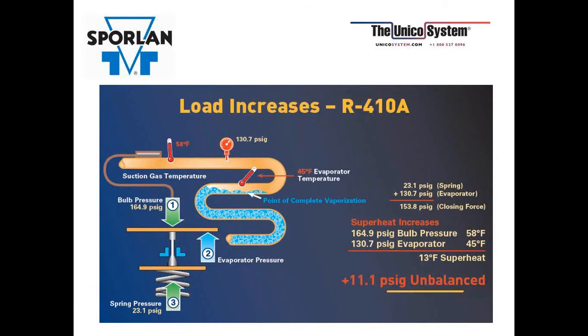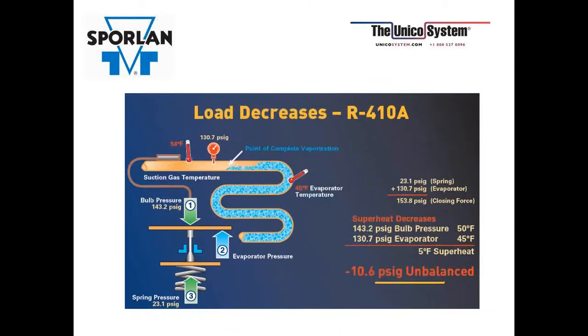So now you're having more superheat coming out of the evaporator to the bulb. The bulb is going to sense it. Now it's 58 degrees versus 50. So that's going to give you an increase in opening force. It's now 164.9. Your evaporator pressure and your spring pressure in this case are staying the same. So now the valve is going to stroke itself open to a more open position, trying to get itself back to a balanced state.